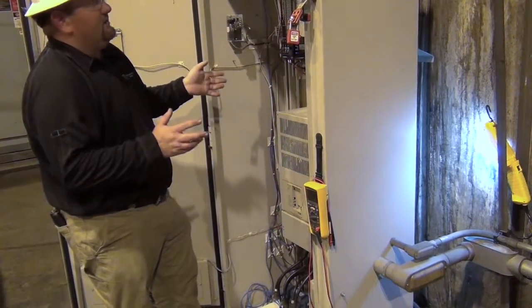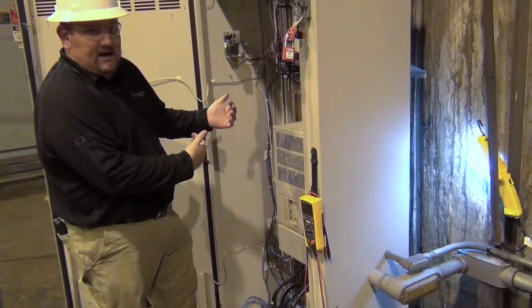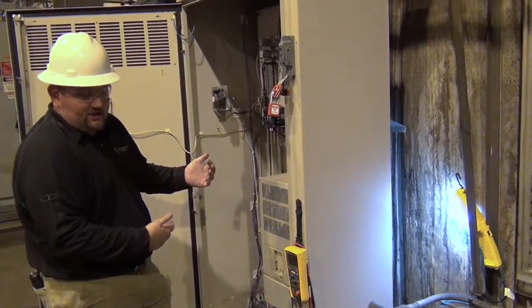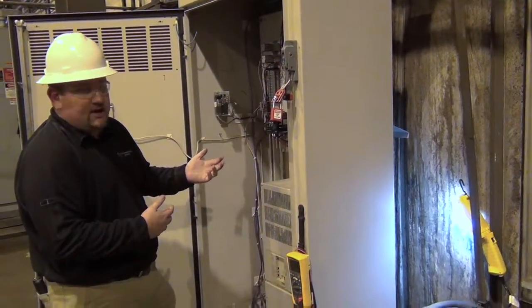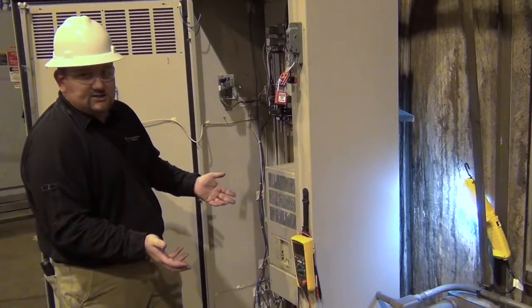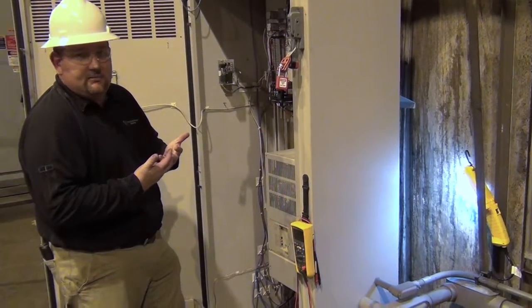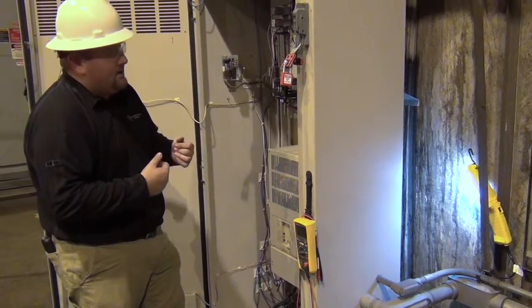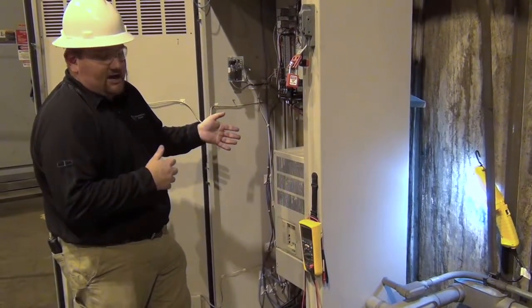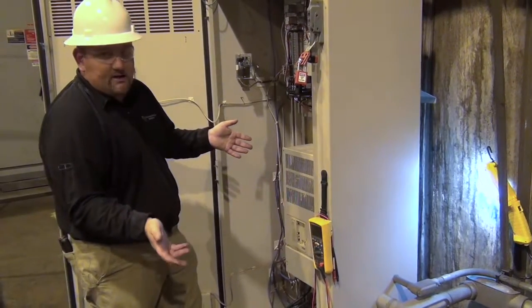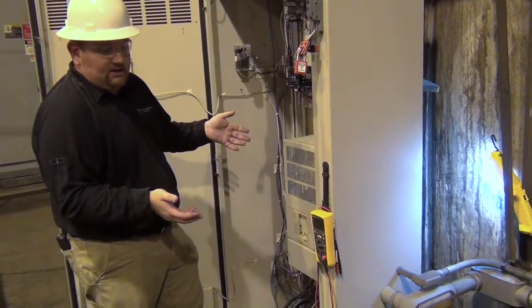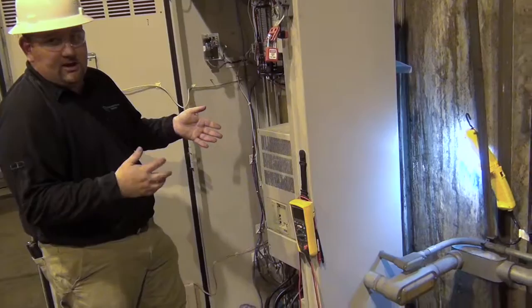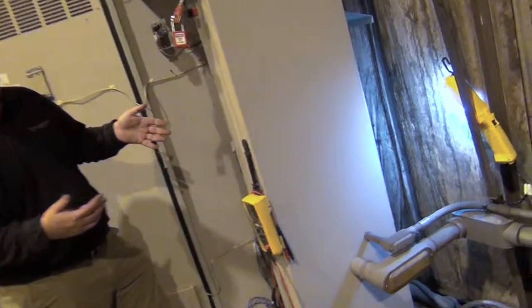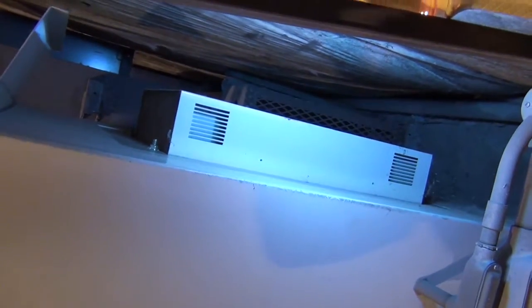With the installation environment of this one, I have to kind of fit behind the machine, so it's not practical to have both the vacuum and the air compressor. The most important part is to get the dust and dirt out from the heatsink and get that area as clean as we possibly can. So I'm going to go around to the back of the drive and reach back there as best I can with the air compressor. And again, the key thing here is you want to have low pressure. You don't want to be at 100 psi. You always want to blow from the bottom of the drive and force the air and the dirt up the heatsink as the cooling fans usually would.